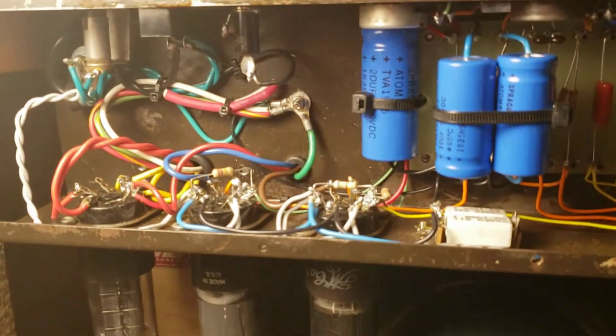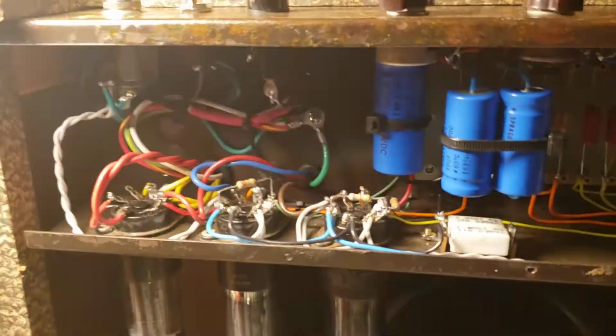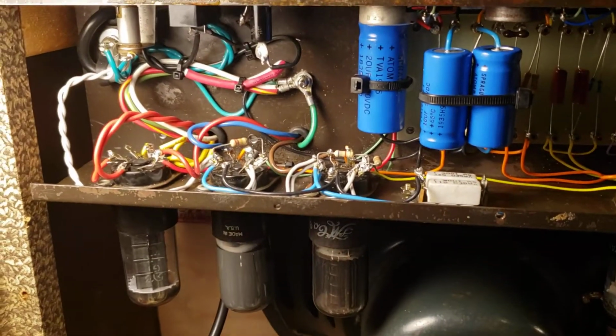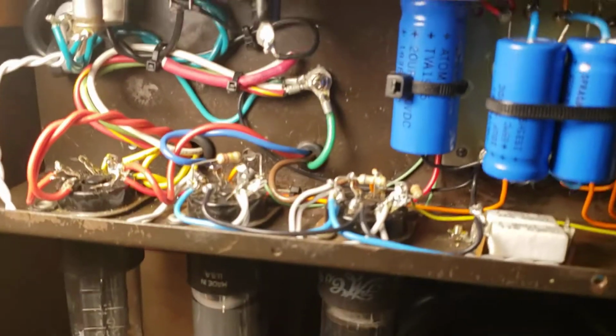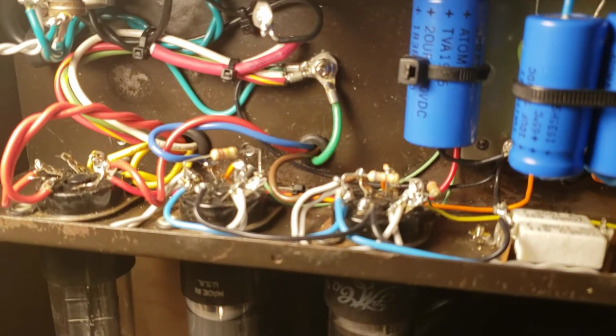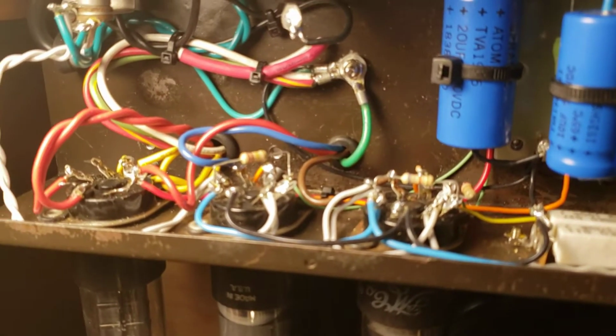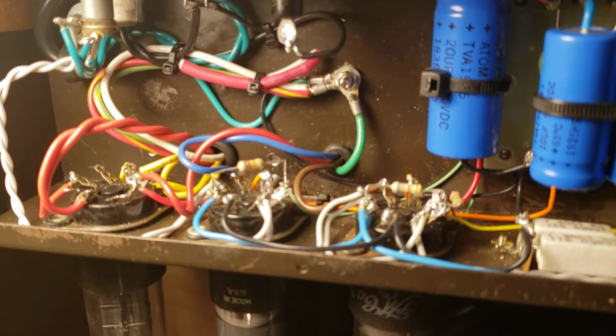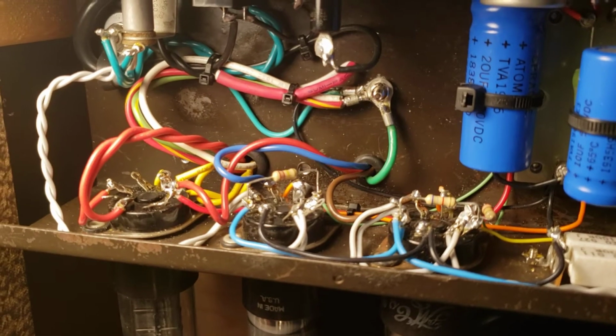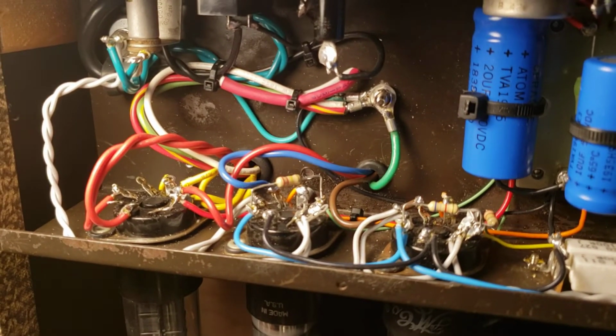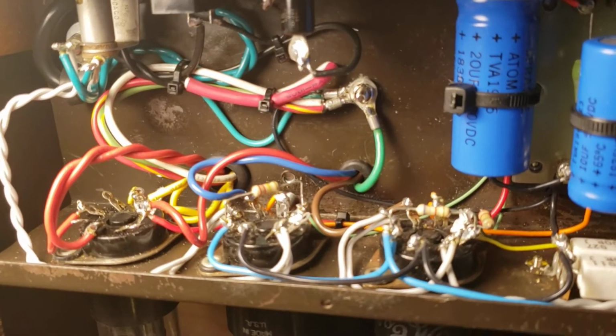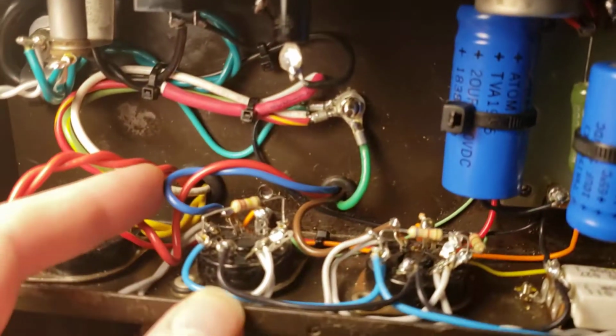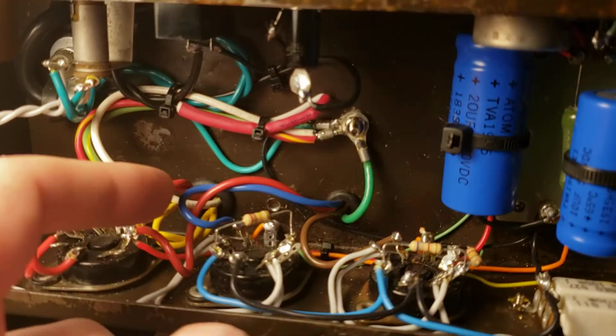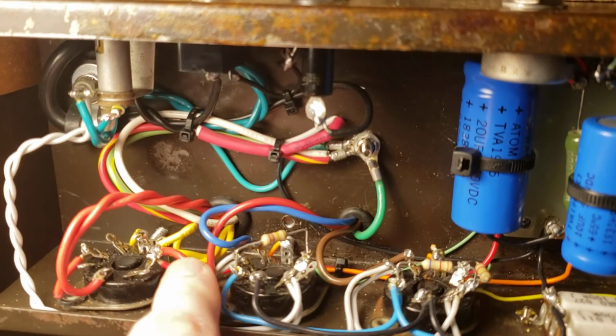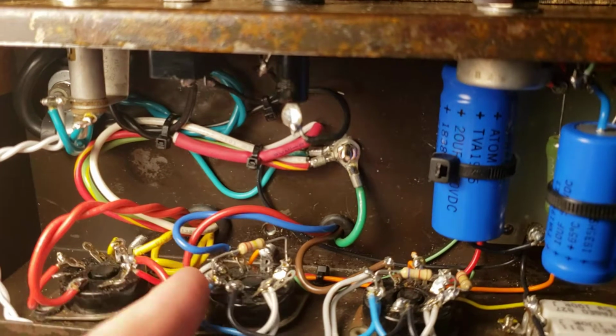Now, when you install new transformers, there's always a balancing act between tidying up the wires neatly and leaving enough behind so that if you have to work on those terminals again, you have enough excess wire and aren't trying to splice or stretch the wire as tight as a guitar string. So I've left a little extra of this blue and red wire going to the transformer in case these ever need to be worked on. That's a deliberate little excess - they call that a service loop.